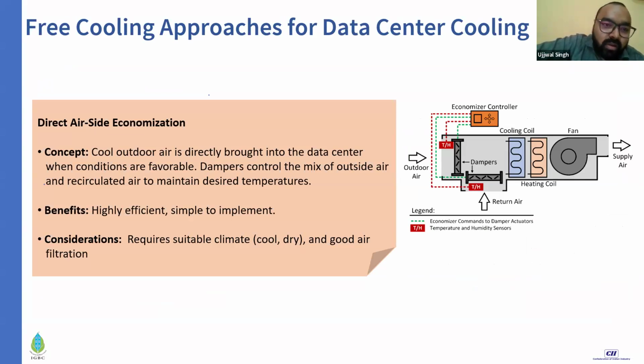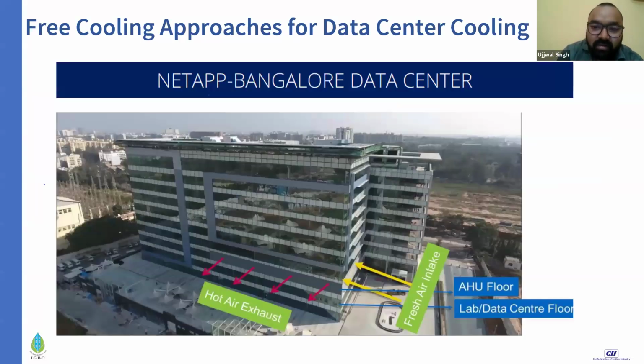Let's first quickly understand what free cooling is. In free cooling, whenever the ambient temperature of air is less than the allowable supply air temperature to your data center, you bring that fresh air inside. After some filtration and measuring the air quality, you bring that air inside, cool your data center with that air, and then throw that air back to the environment as your sink. This is the actual image of a data center of NetApp that is placed in Bangalore, India. From the arrows, you can see that fresh air is getting taken in from one side, and after cooling, the hot air is getting exhausted from the other side.